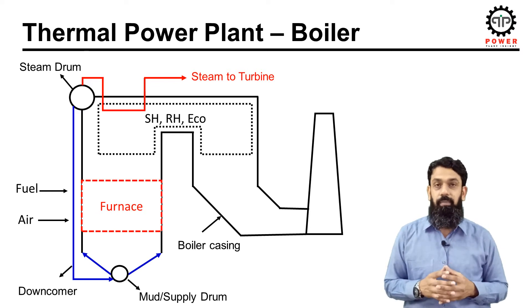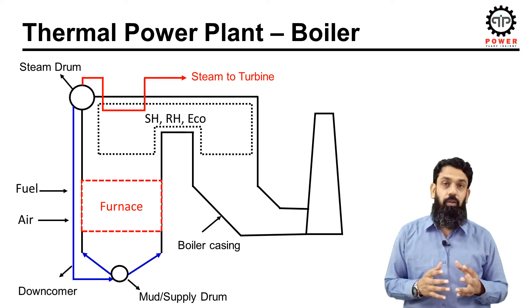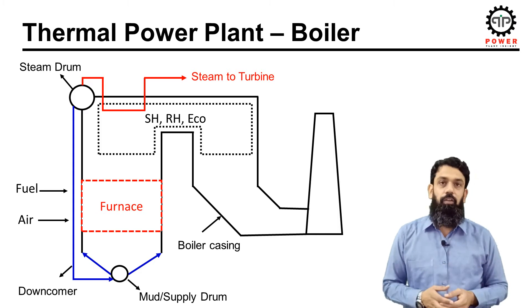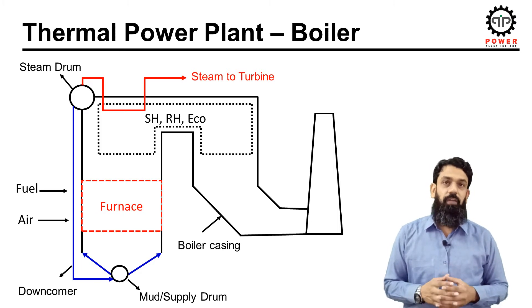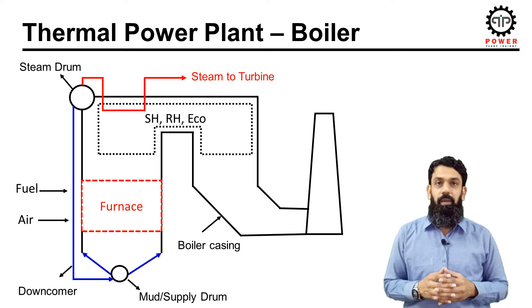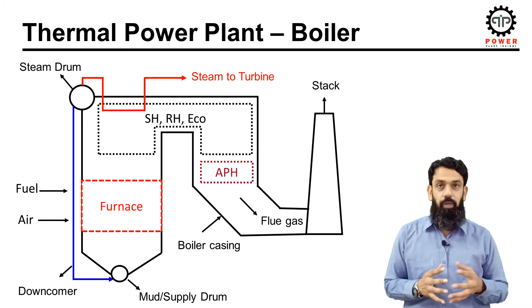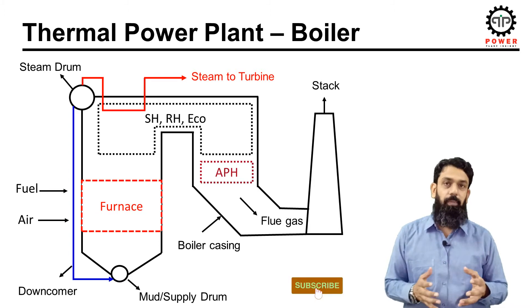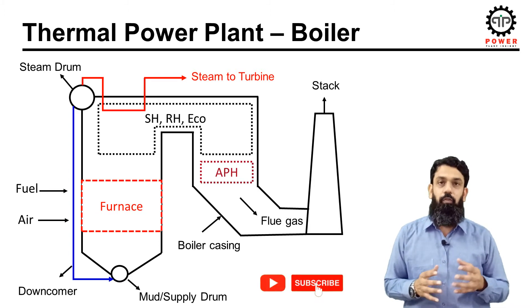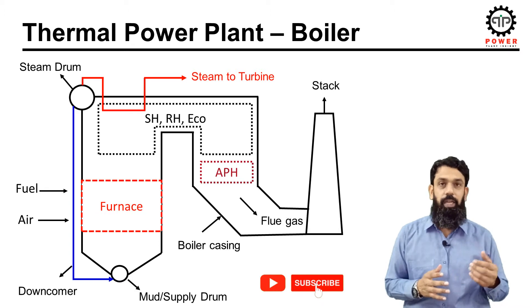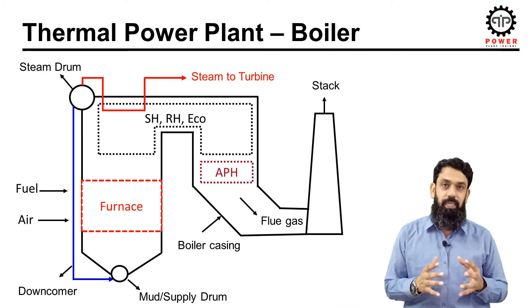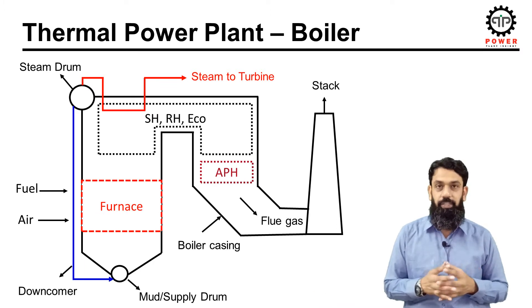The mud drum or supply drum equalizes the distribution of water into the water walls of the furnace. Flue gases, after transferring heat to the tube bundles, flow through the air preheater, whose main function is to preheat the combustion air for the boiler. After passing through the air preheater, flue gases are discharged into the atmosphere through the boiler stack. This was the basic and general understanding of the boiler and its configuration; we will discuss the boiler in more detail in upcoming sessions.